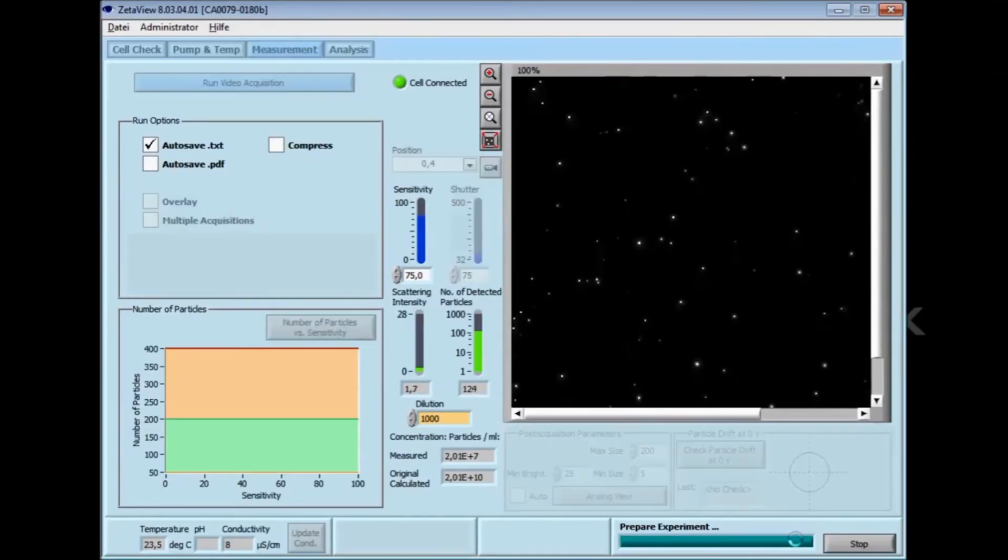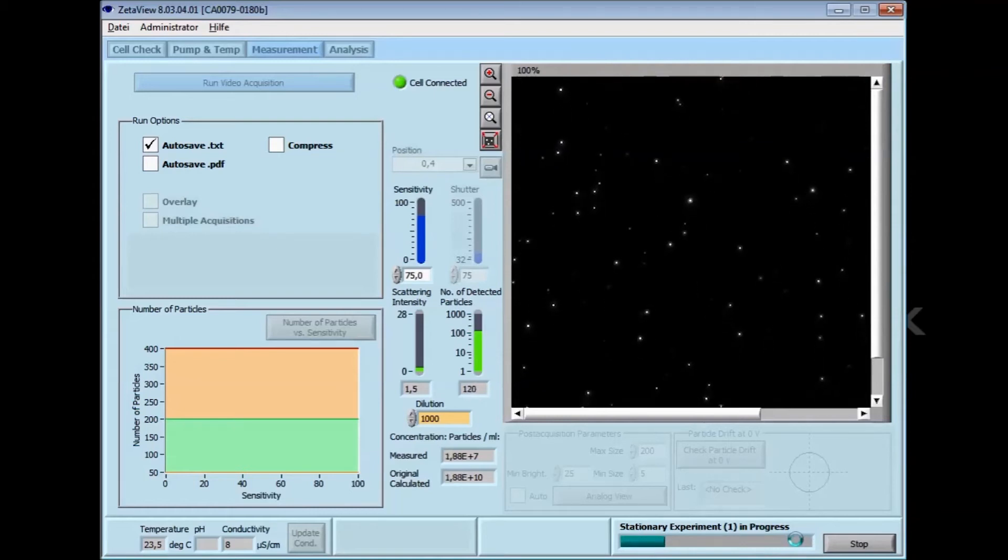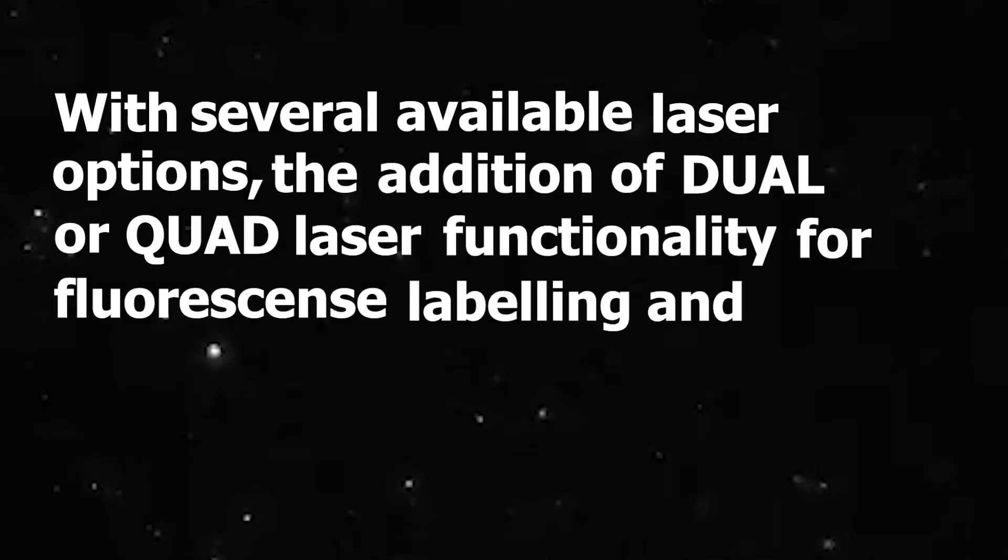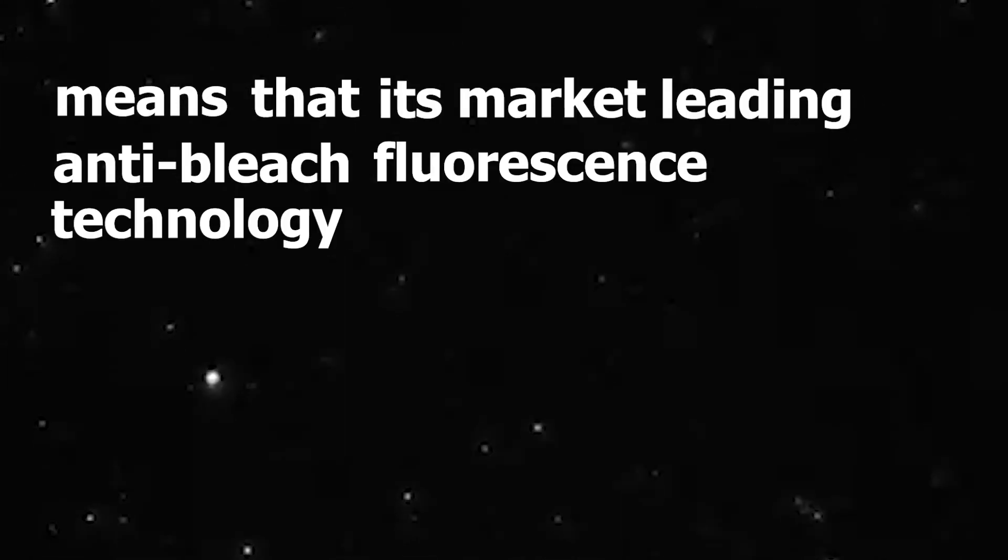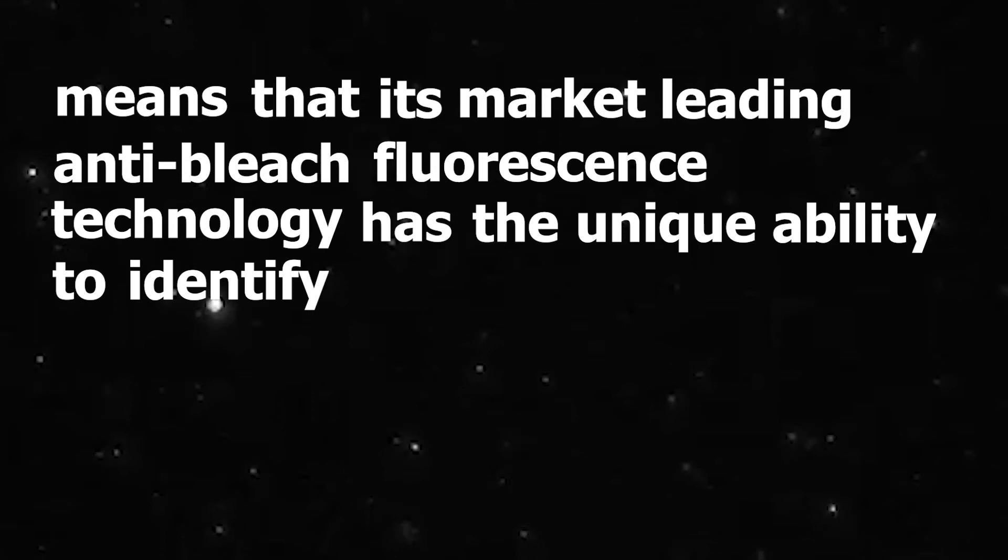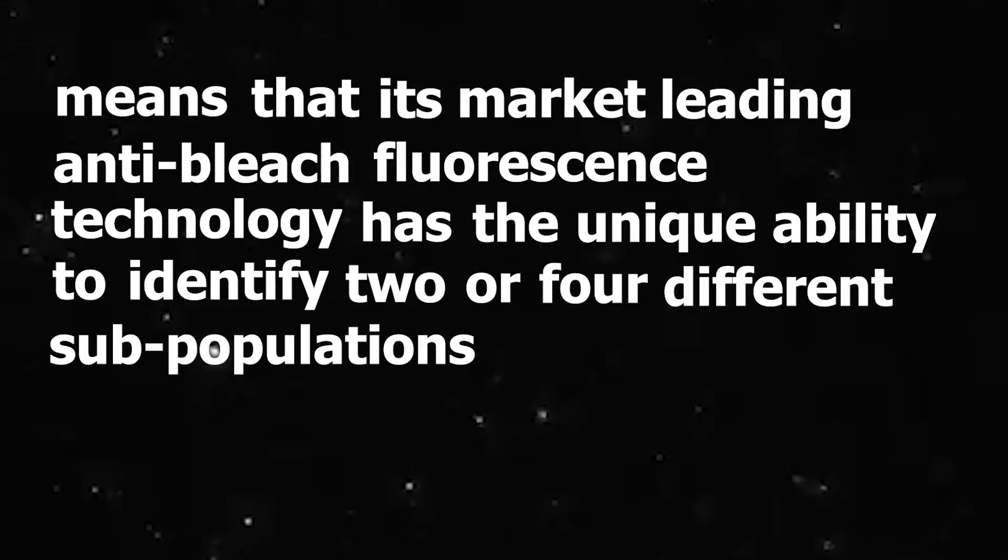These parameters can be measured both in scattering mode and fluorescence mode for the determination of fluorescently labeled subpopulations. The ZetaView can measure particle size between 20 nanometers and 1000 nanometers, dependent on sample and laser. With several available laser options, the addition of dual or quad laser functionality for fluorescence labeling and multi-wavelength excitation means that its market-leading anti-bleach fluorescence technology has a unique ability to identify two or four different subpopulations in quick succession, without the need to manually change lasers.